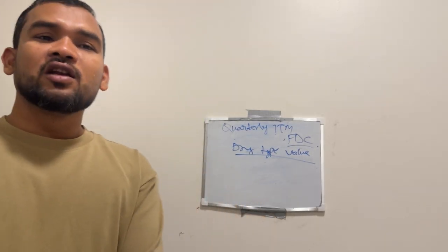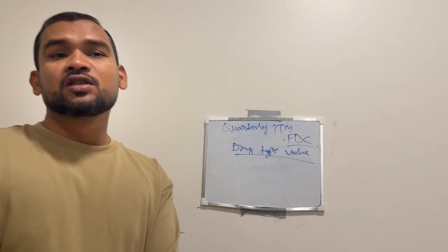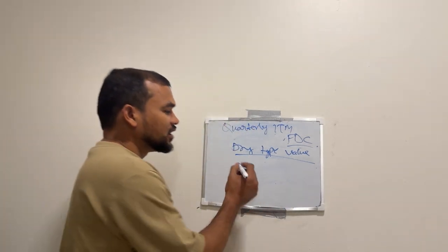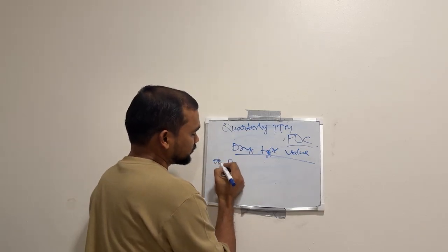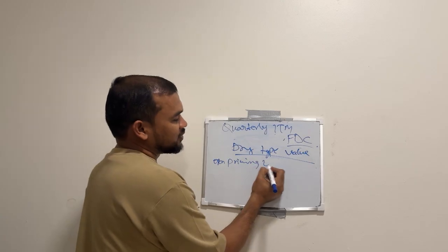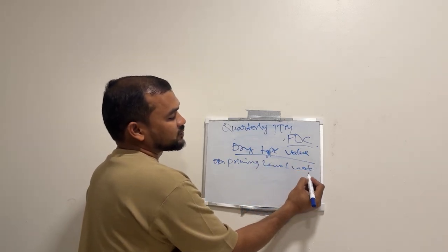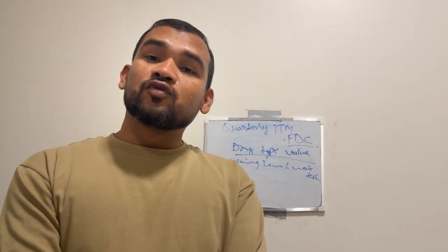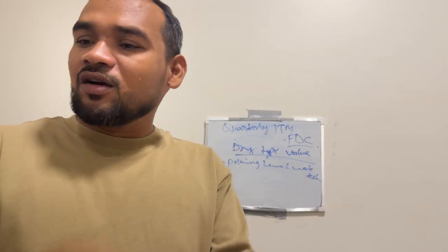And what is the priming water level test, how will we do this? First we will open the priming level water test. We have to slowly open the test valve to check whether water is flowing or not. We allow water flow until air is heard, and we check that air is going outside. If air discharges, immediately close the valve and check whether there is any problem or it is okay.